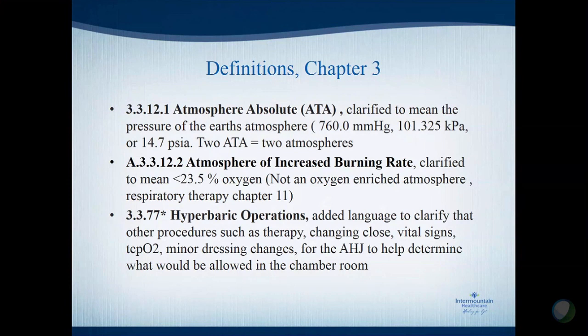We added the definition of hyperbaric operations. As you know, CMS in their infinite wisdom, and then the Joint Commission, has adopted it. So the surveyors are using the NFPA 99 2012 edition, and they're coming into environments such as ours. The old language talked about the room housing the chamber shall be for the exclusive use of the hyperbaric facility. Well, what if you want to do a little wound care or something like that?